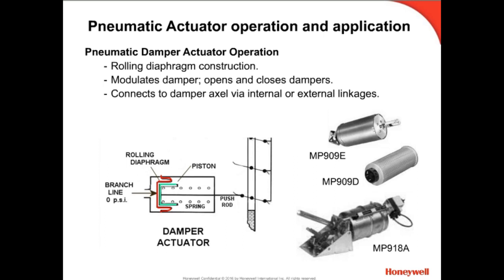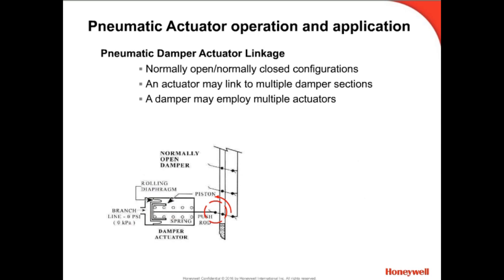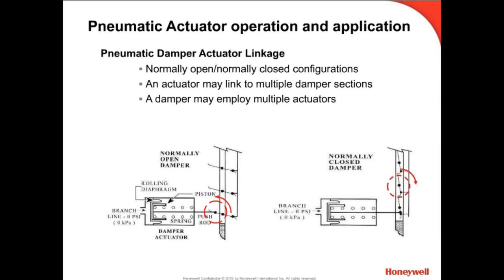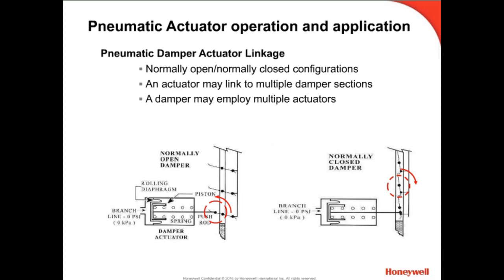A damper is configured normally open if the actuator return spring pulls the damper open. In this diagram, the damper axle is rotated counterclockwise to open, providing the normally open damper configuration. A damper is configured normally closed if the return spring of the actuator pulls the damper closed. In this diagram, the damper blade axle is rotated clockwise to close, providing the normally closed configuration. Because the return spring will return the damper to its normal position on a total loss of air pressure, this position is also referred to as the fail position.